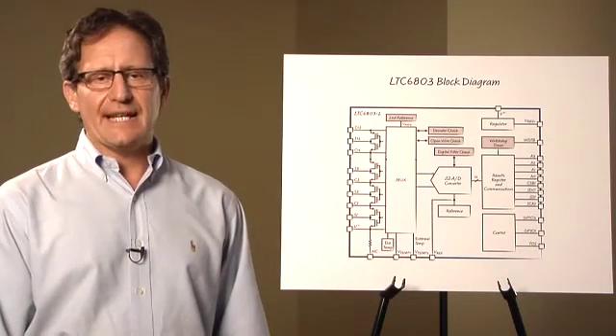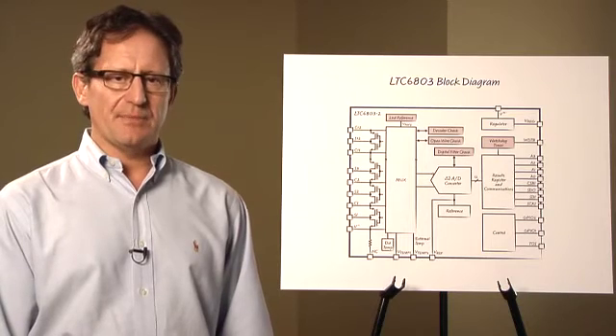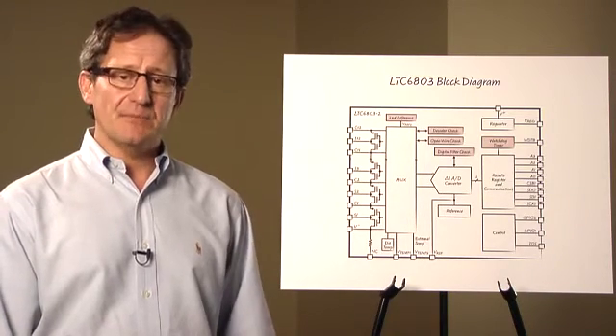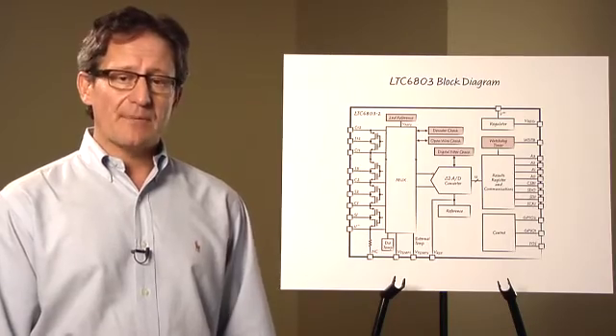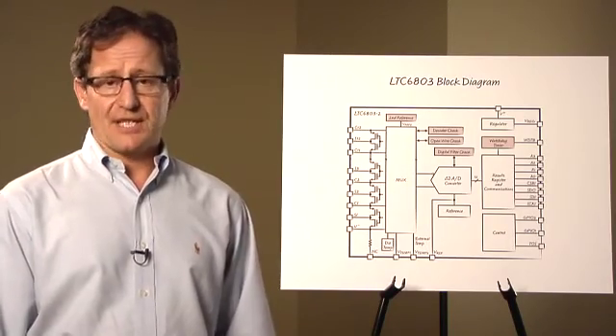In order to verify the proper operation of any data acquisition system, you must measure an independent voltage. Measuring the second reference provides this independent verification of the primary reference and the input stages of the ADC.